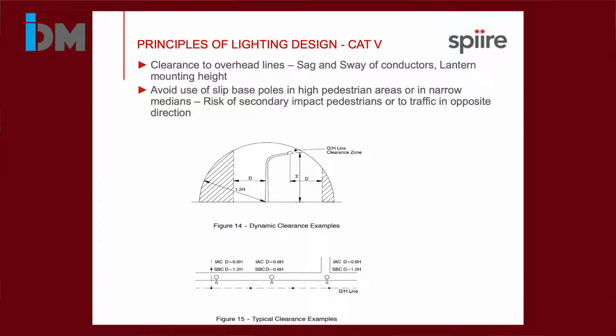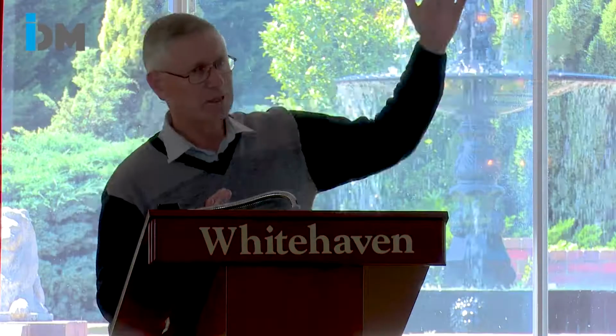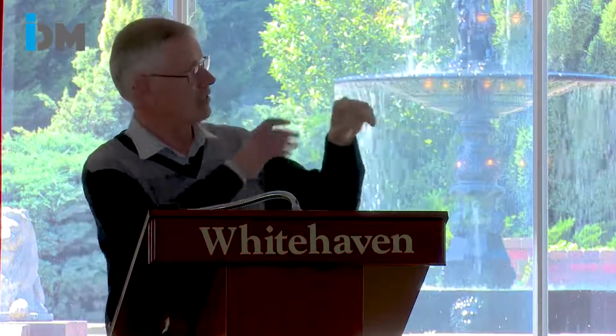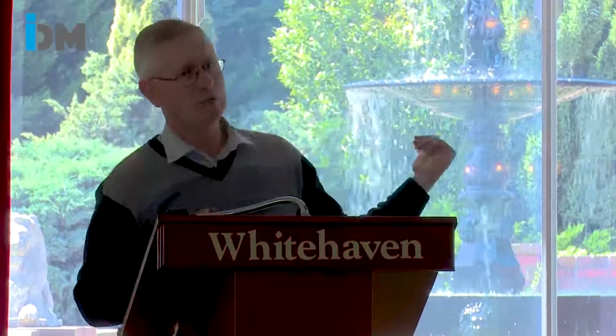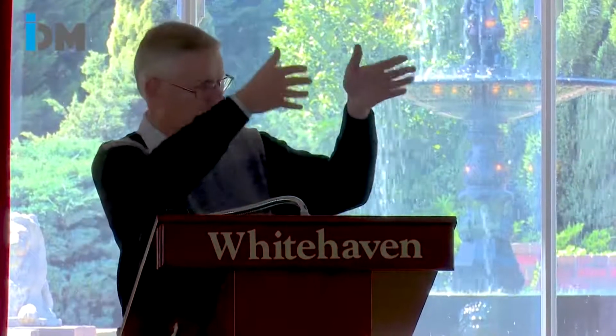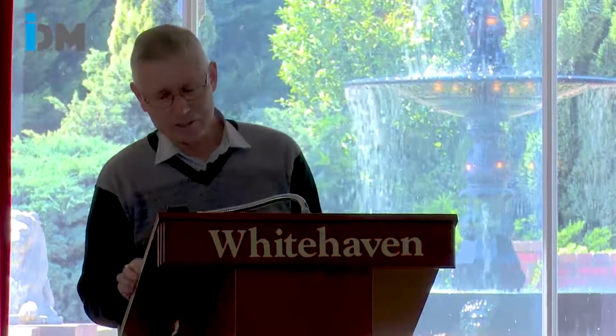So if you've got a mounting height of 12.5, you've got to have around about 7.5 metres physical separation between the pole and the nearest conductor. But that nearest conductor is not static clearance on a still day. It's actually maximum sag of that conductor and maximum sway with a stiff wind blowing it sideways. So you also got to allow for sag and sway. And typically that's something that lighting designers will miss.